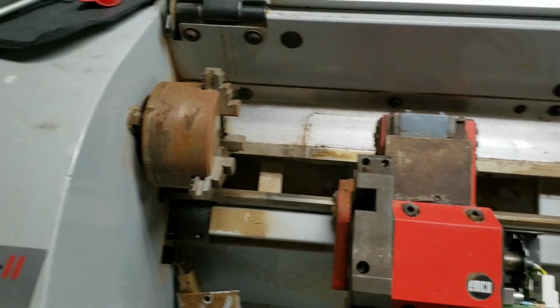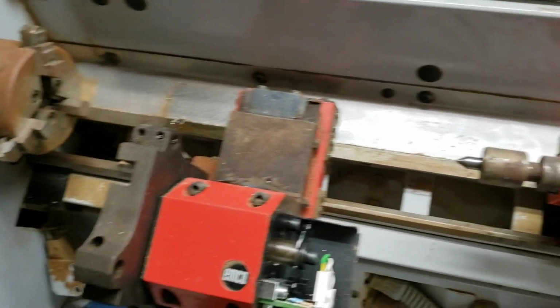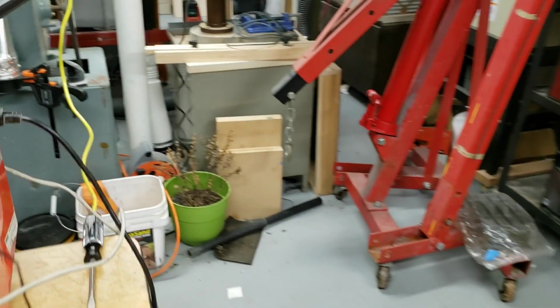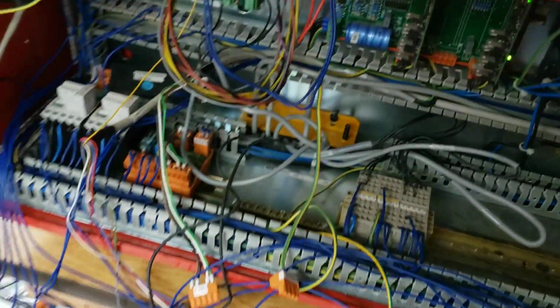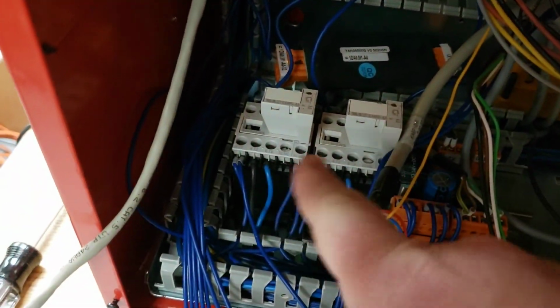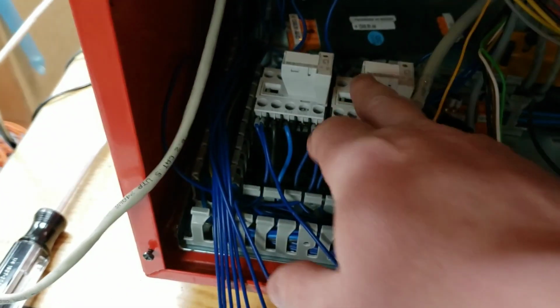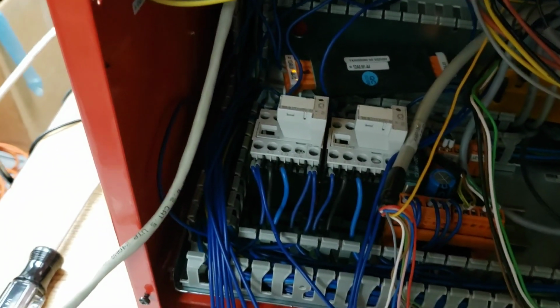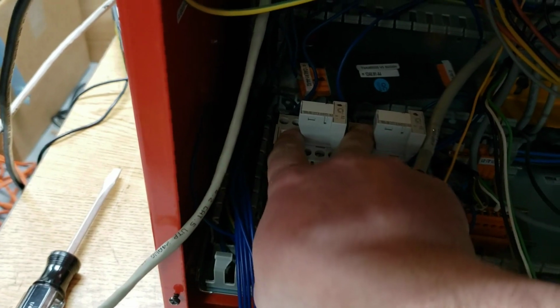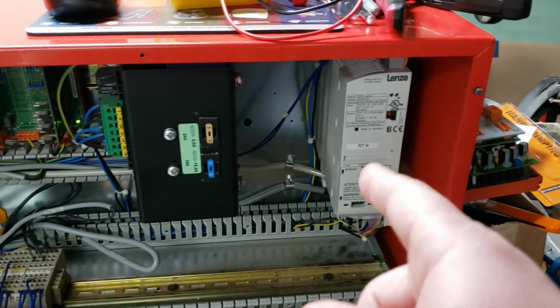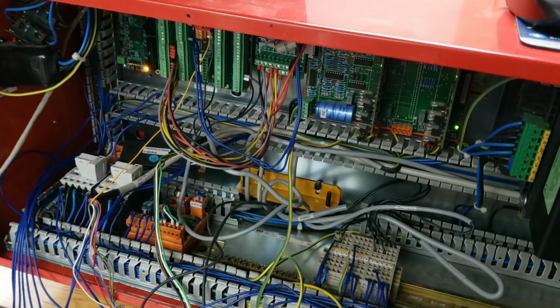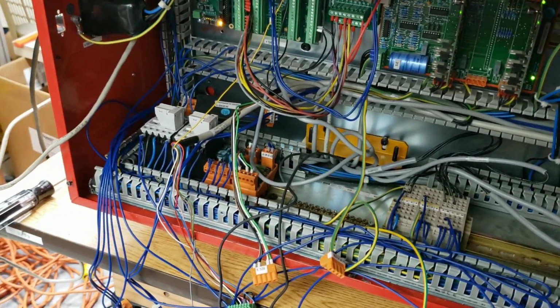Next project is getting the VFD hooked up. I have to trace out some of these wires still. I can't get the contactors to come on, that's why I've got the spaghetti incident going on here. I can't get these contactors to trip on. There's 24 volts that's got to go to these to power the VFD. I did toggle the manual overrides yesterday, and the VFD did kick on, so I know there's life in that thing.